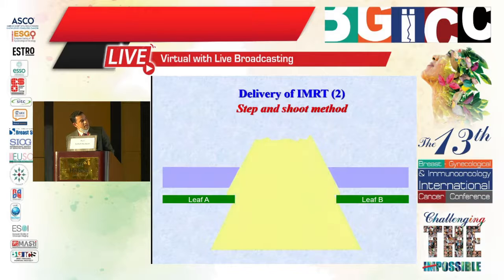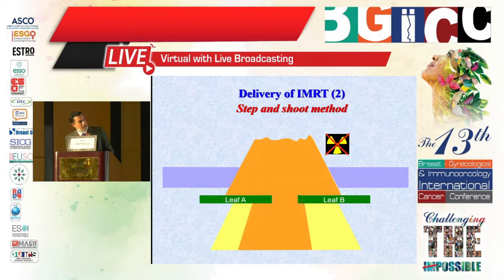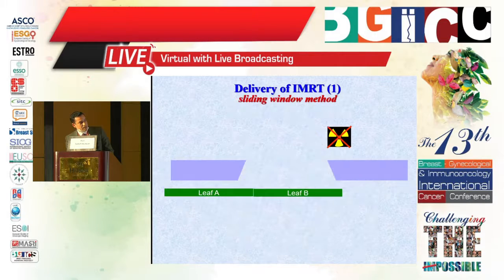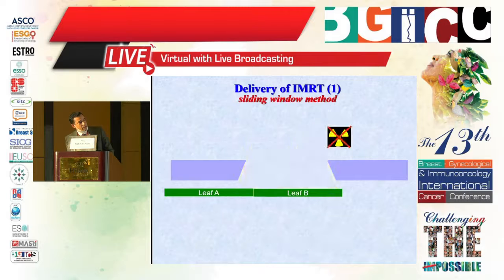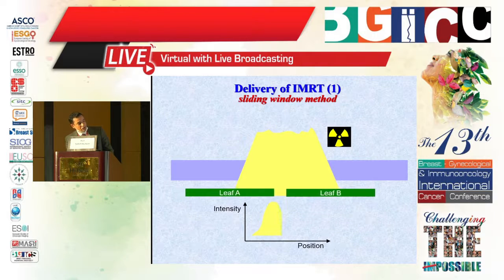Methods of IMRT delivery: the step-and-shoot method, where the radiation turns on and off and the MLC starts and stops at different positions to give the intensity map; and the sliding window method, which depends on continuous MLC motion with continuous radiation.